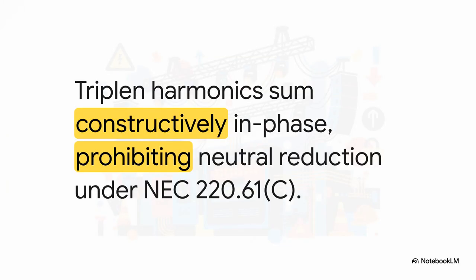The really crucial point here is how these harmonics behave, specifically what we call triplen harmonics. Those are odd multiples of the third harmonic, like 180 Hz or 540 Hz. In a normal three-phase electrical system, balanced currents beautifully cancel each other out on the neutral wire. But triplen harmonics, they do the exact opposite.